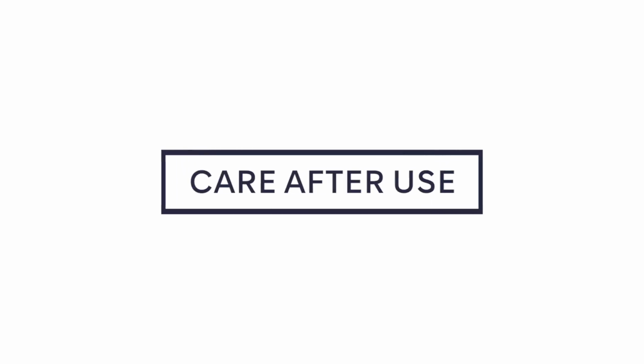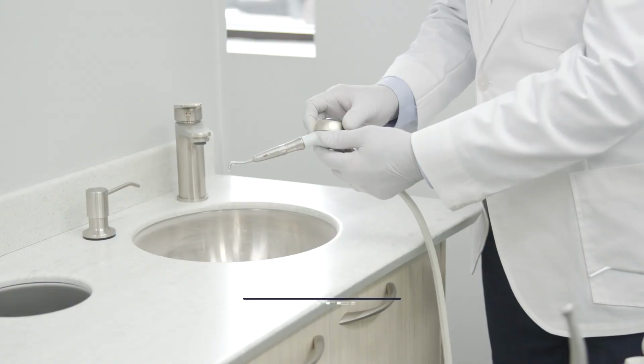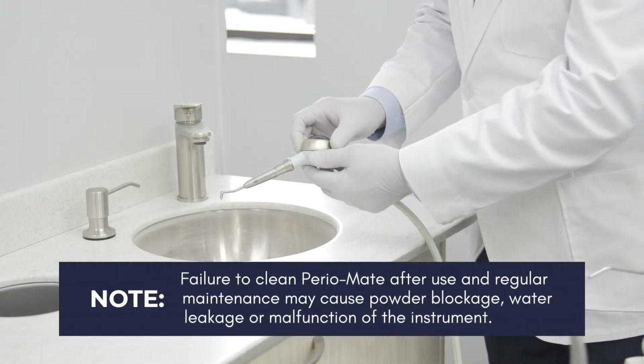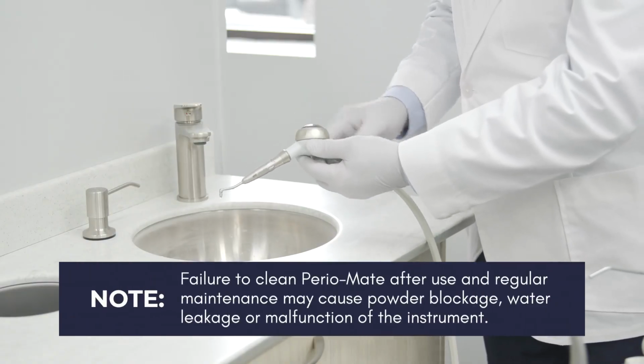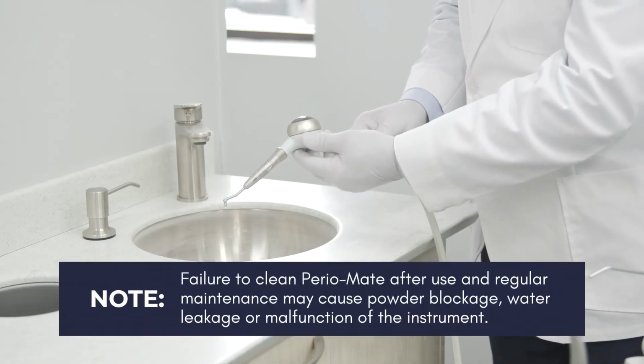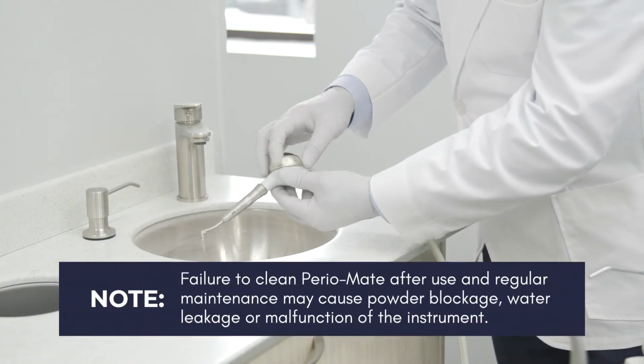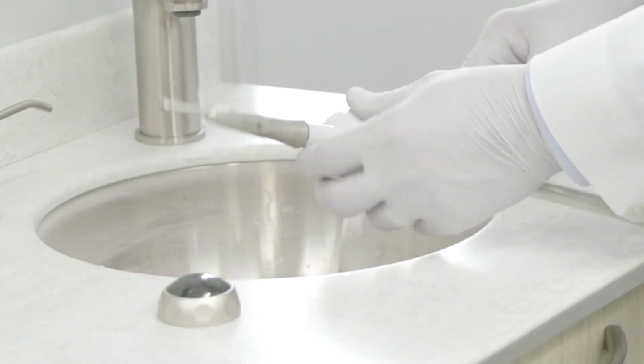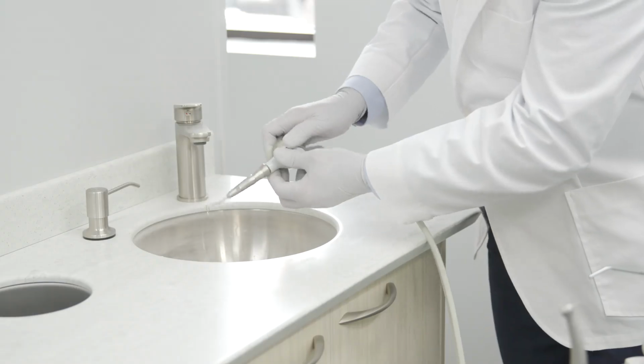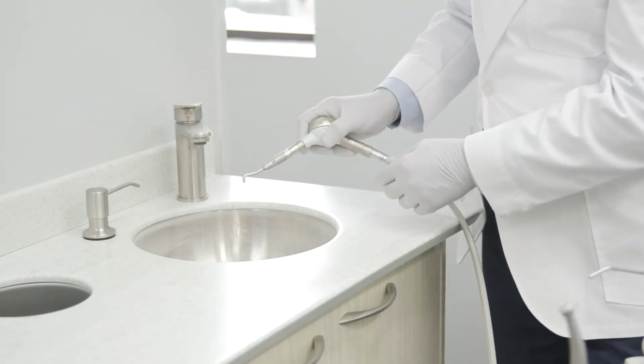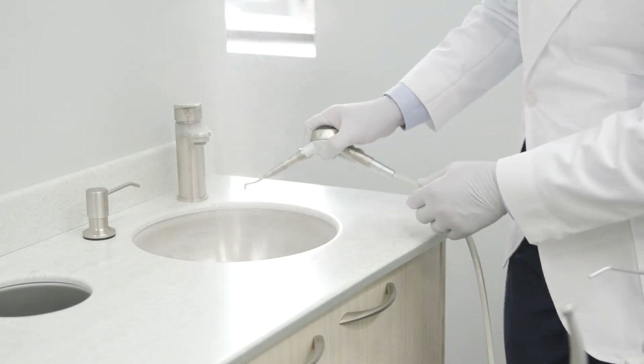Care after use. Note: failure to clean Perio-Mate after use and regular maintenance may cause powder blockage, water leakage, or malfunction of the instrument. After removing the remaining cleaning powder in the powder case, close the cap and run Perio-Mate with air only to discharge water and powder in the nozzle.